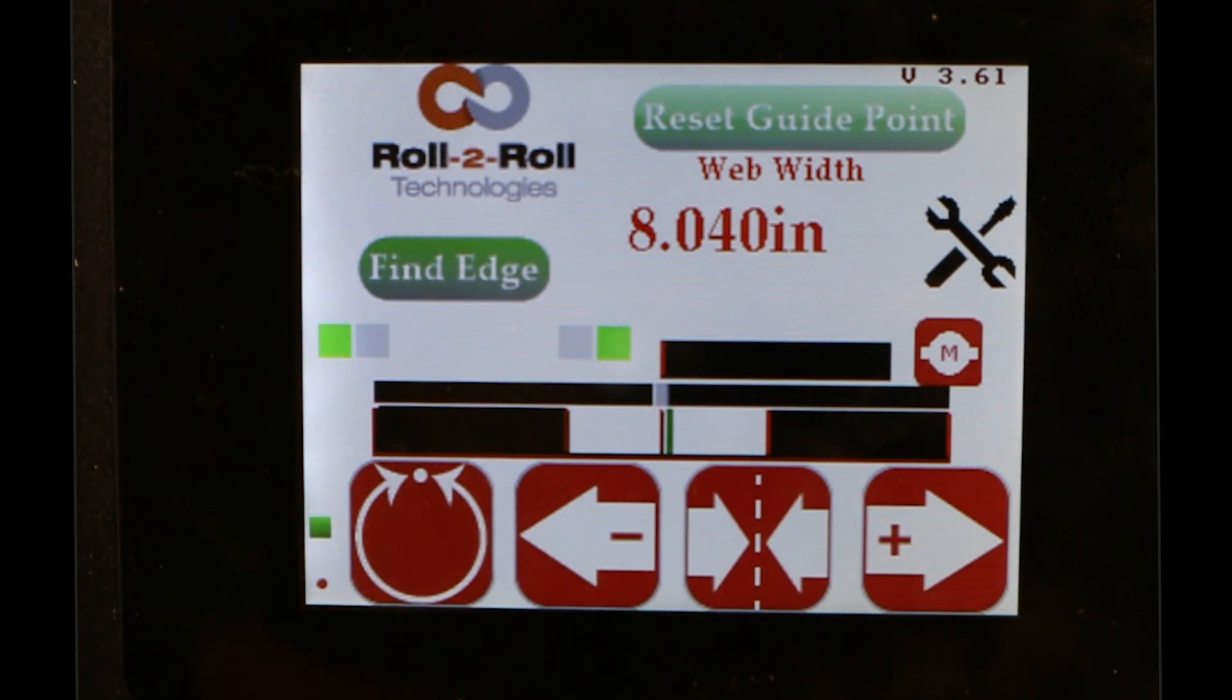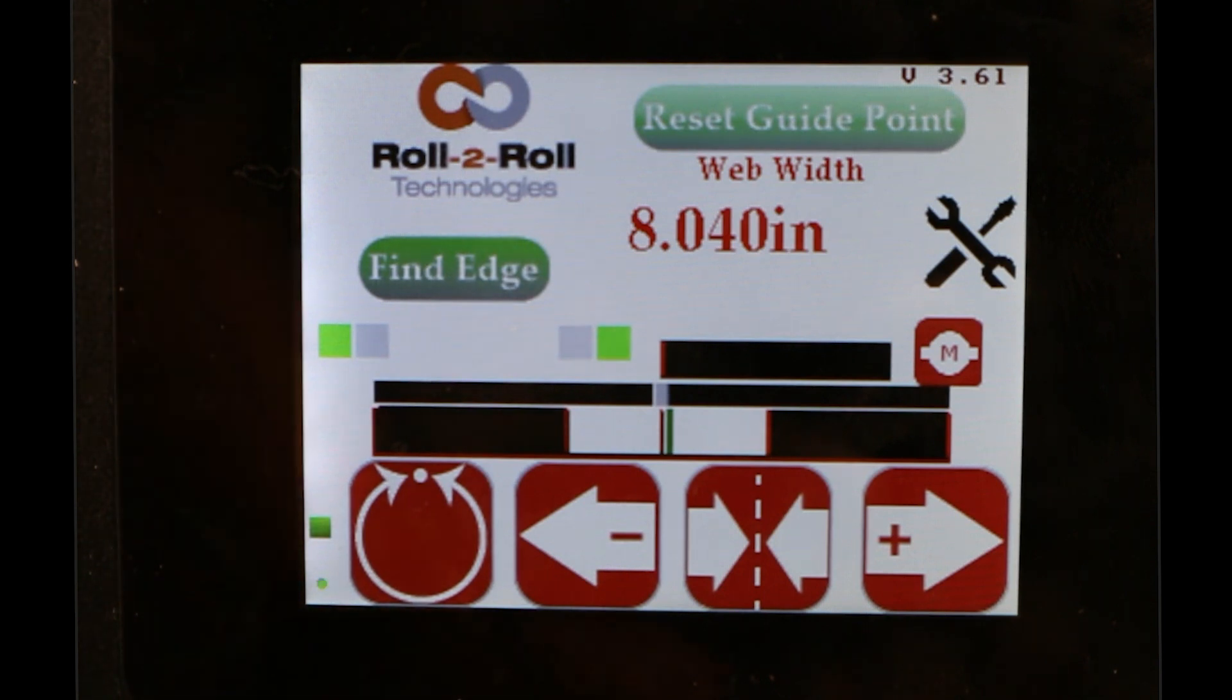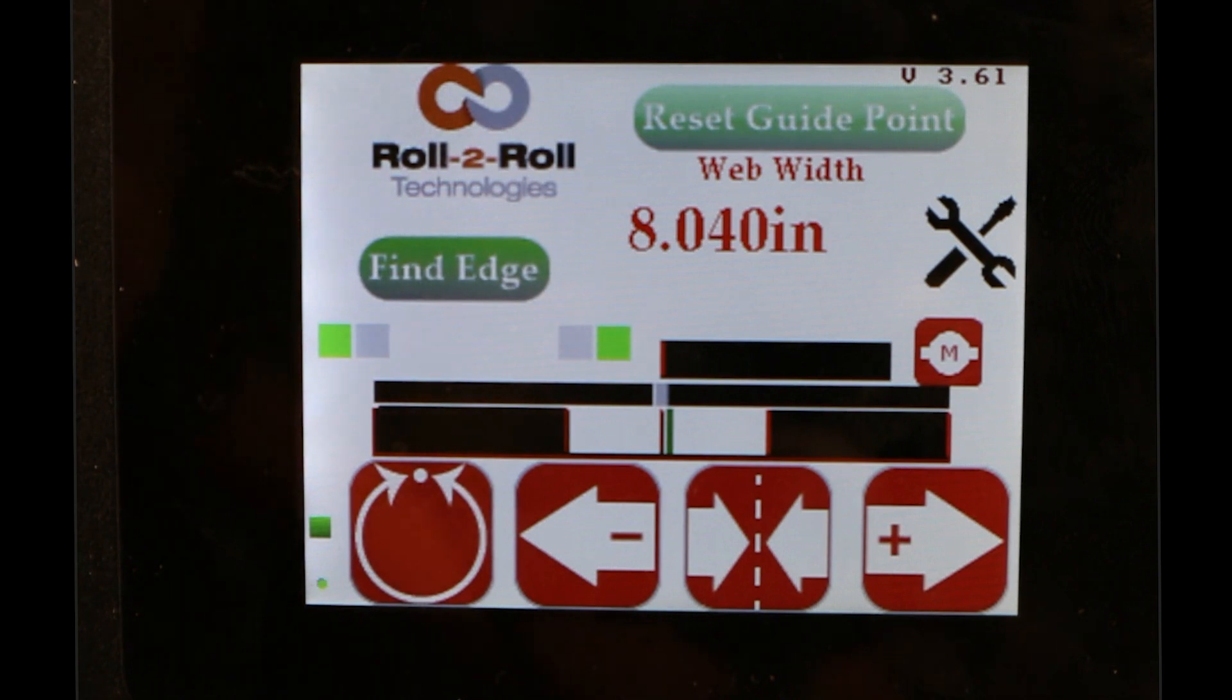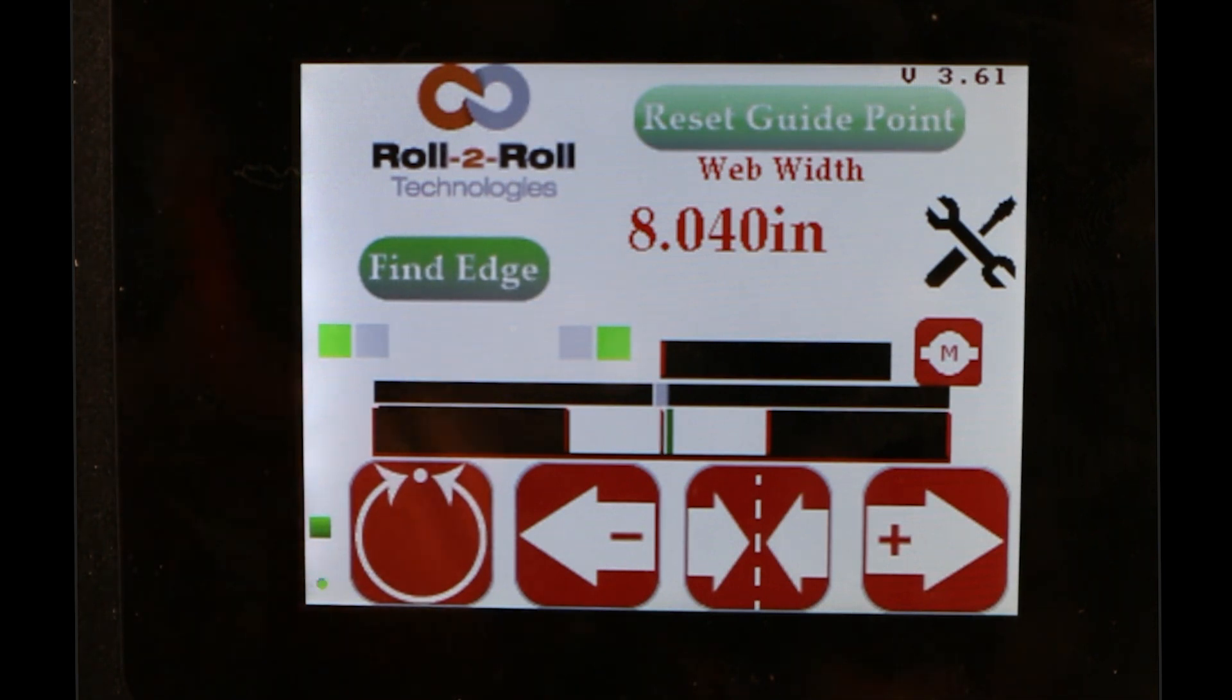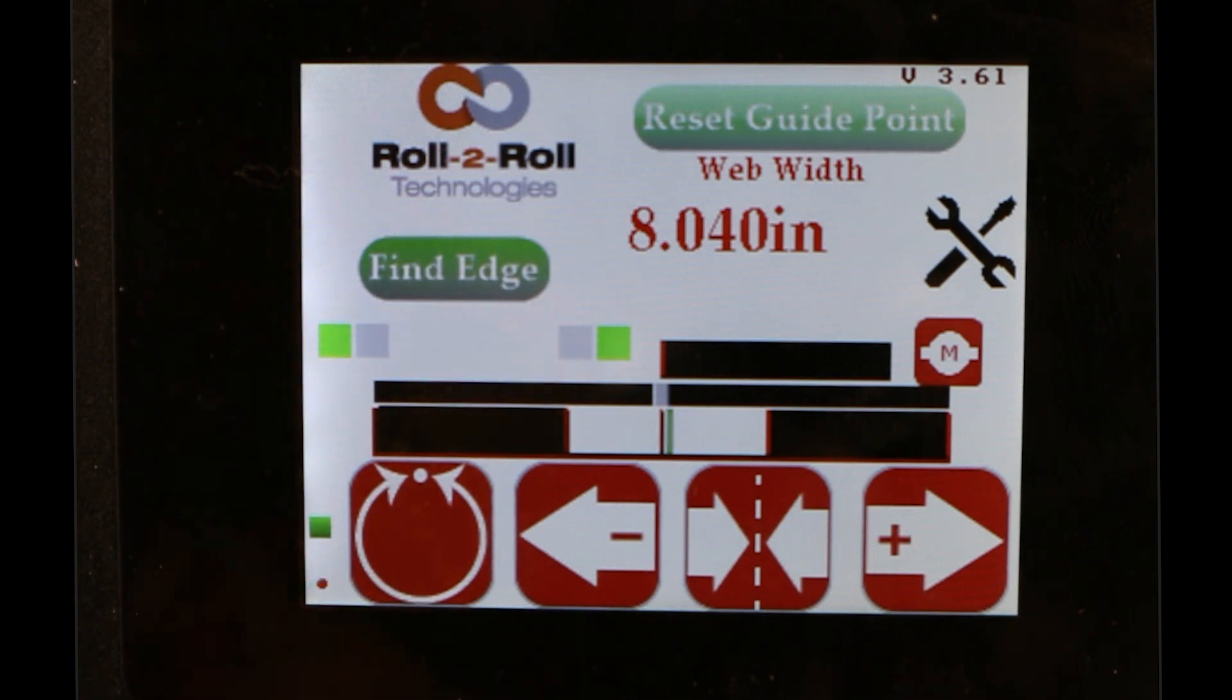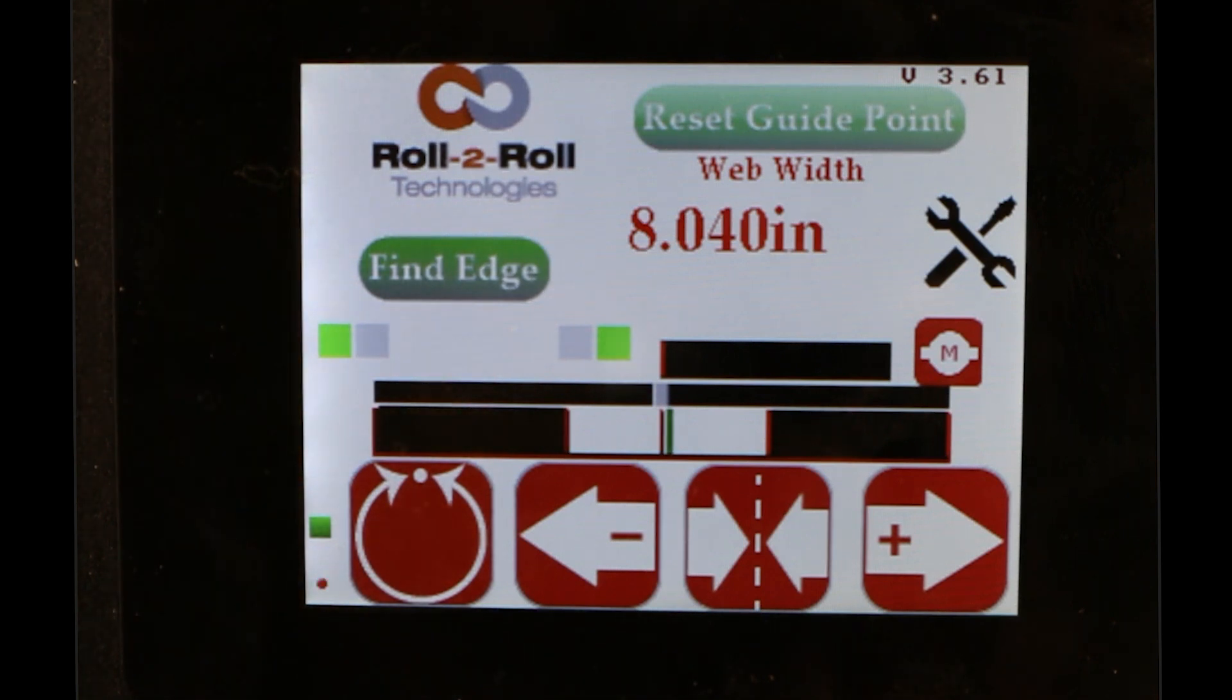The analog output is going to provide a value that is whatever the portion of the left edge of the sensor is and whatever the portion of the right edge position of the sensor is, those proportional value is what is going to be output on the analog output. If you are using an analog to digital converter to look at that value, you still need to know the distance between the two sensors to find the absolute width. The output will always provide you the relative width without the distance between the two sensors.